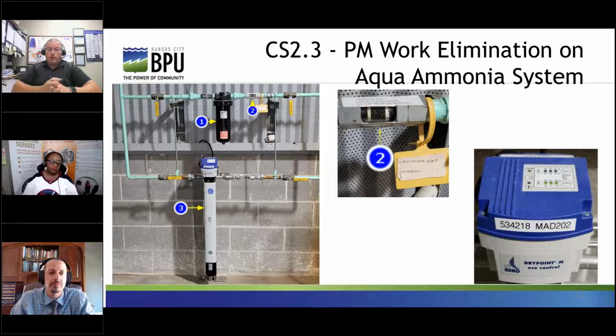They would then issue a work order to dehydrate the saturated desiccant beads. This is affixed to those PM work orders. Number 3, a desiccant membrane dryer was selected to replace a second desiccant dryer, not pictured. It is sized for the system and has completely eliminated the PMs to dehydrate saturated desiccant beads.